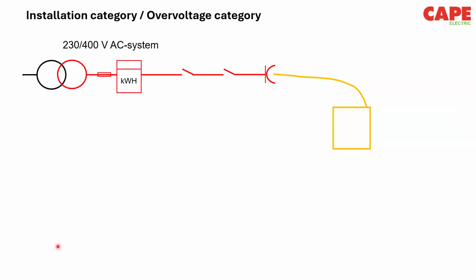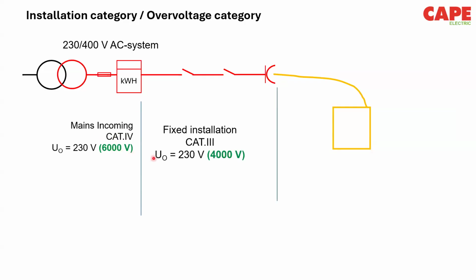So how do we select an SPD, or why do we provide an SPD to your building? So you know that in our building, there are four categories. So category 4 is at the mains incoming. So your power meter, your MCB, your MCCBs, all your circuit protected devices are tested for an impulse withstand voltage. So this impulse withstand voltage is 6 kV for your mains incoming. Okay. Your fixed installation, in the sense lights, maybe even some ACs, TVs, any other fixed installation, fridges, are tested for 4 kV lightning impulse. And then connected device is tested for 2.5 kV.